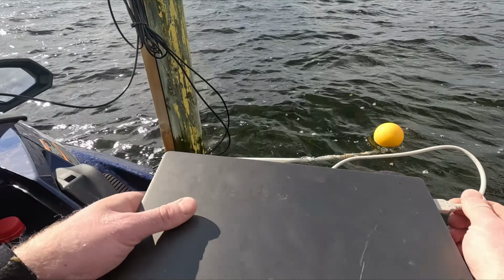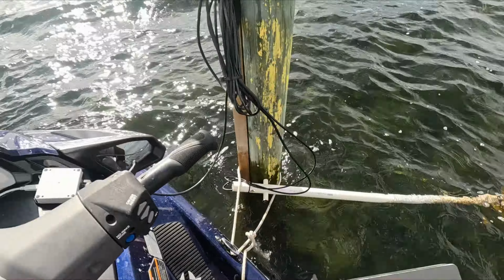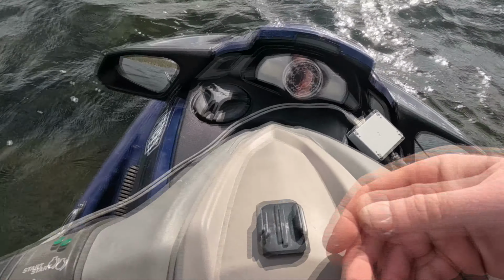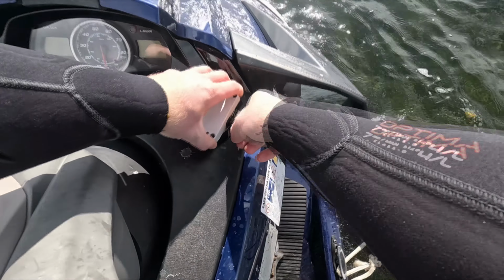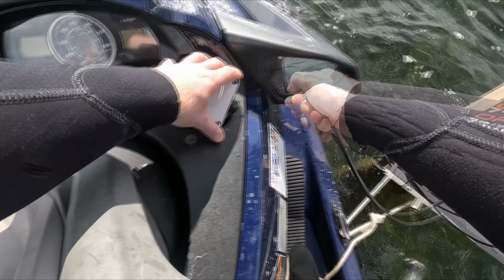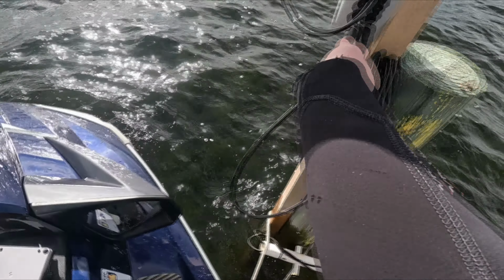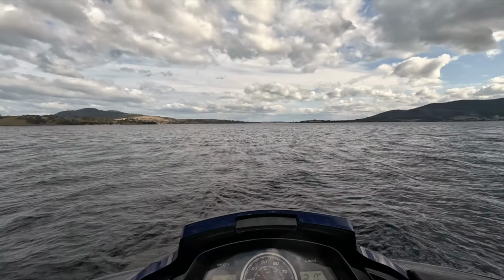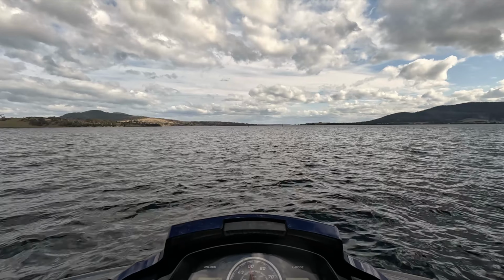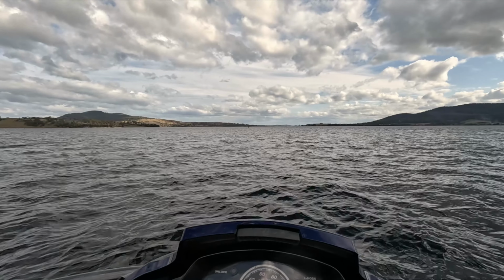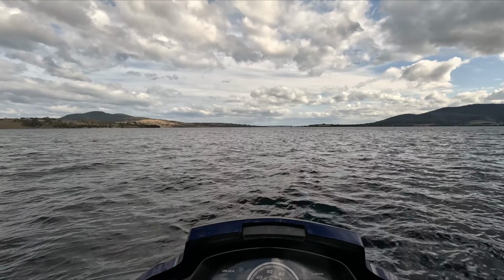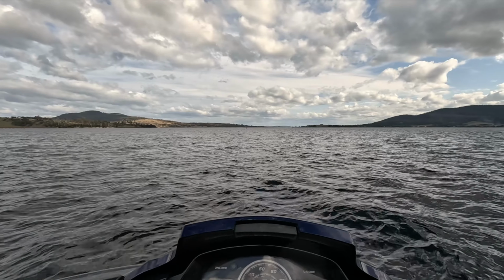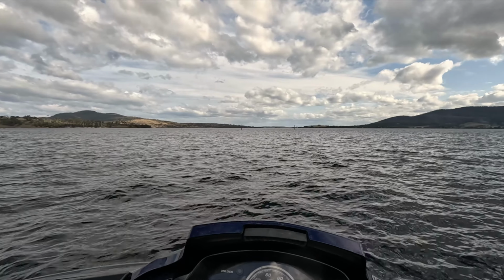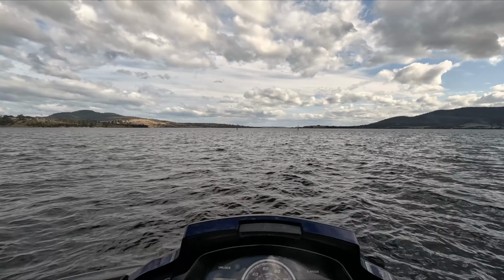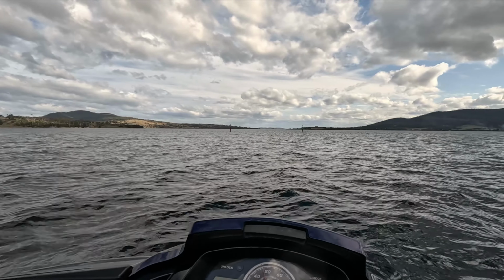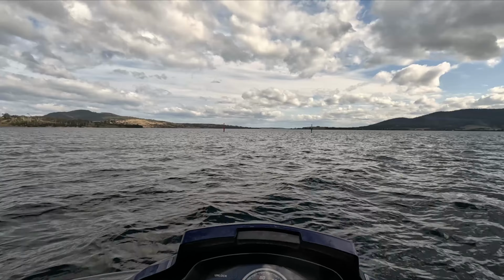Now we can return the sensor to the node. And we're done calibrating for this site. This calibration process at the minute is a little bit painful. It does mean that we need to be on site, unplug the sensor from the box, plug it into a laptop, run some software. It's a bit of a process. We're working on an update for the boxes at the minute that will allow remote calibration of the sensors.